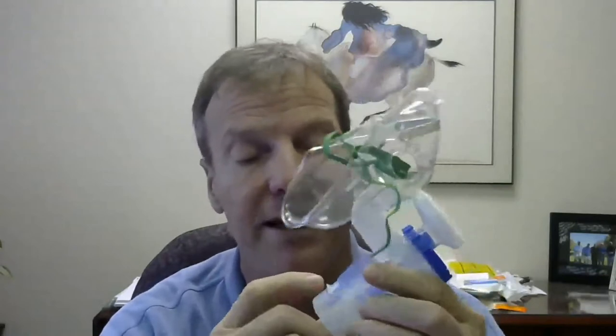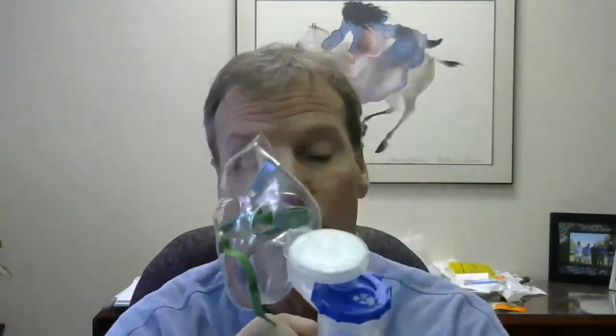I connect the oxygen, I have the option of connecting a very inexpensive filter, and then I can connect a mouthpiece which is also included. I can press the trigger and inhale my medication, release the trigger, and now no medication or flow is going to come out. I can also take the mouthpiece off and attach a face mask. I can put the face mask up, pull the trigger, and take a breath, then release the trigger and take it away. Usually when using a face mask, you might go into continuous mode by pulling the trigger and pushing it down to stay in a release mode, continuously releasing medication.